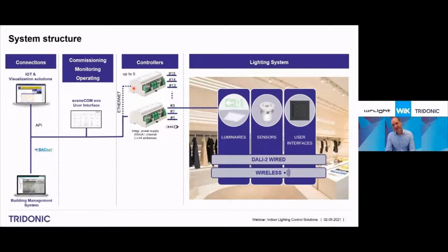In parallel to the web interface, also using the Ethernet IP connection, we have a BACnet IP interface available. So if a sceneCOM evo installation should be connected to a building management system, for sharing data from sensors to the building management system or the other way around, if it's a SCADA system like a building-wide control system for heating, ventilation, air conditioning, elevators, sprinkler alarms, a lot of those systems also have a BACnet interface. Then we can directly exchange data from the light management system to the building management system or other systems, or the other way around, where external systems can also send data or partly control our sceneCOM evo systems. That's all available via the integrated BACnet interface.